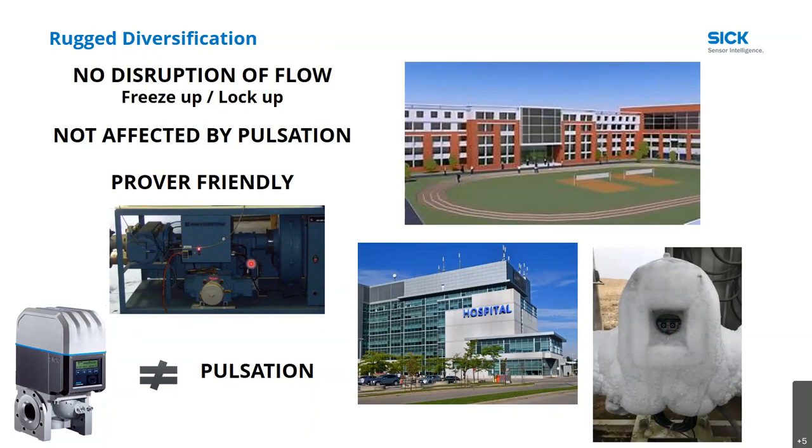It's prover friendly, which means if you wanted to use a prover to verify the meter performance out in the field, you could. It's not affected by any kind of pulsation upstream of the meter, so you can mount regulators or a valve very close to the meter itself.